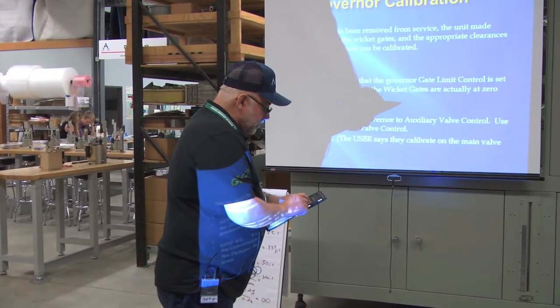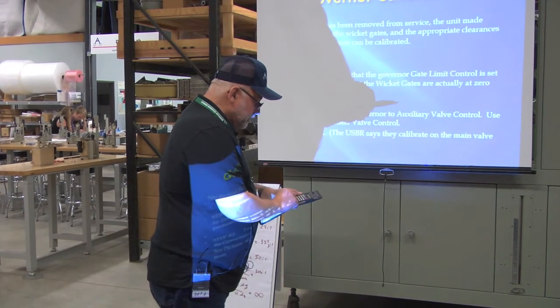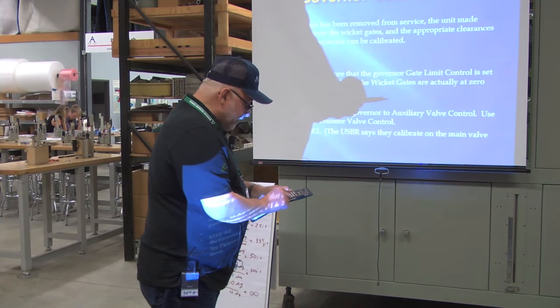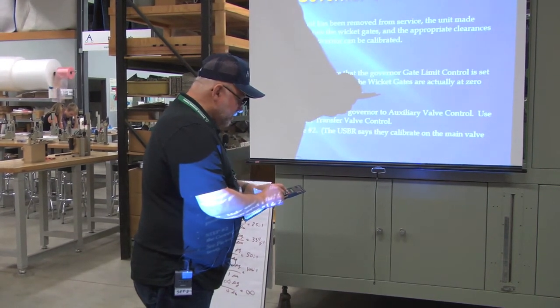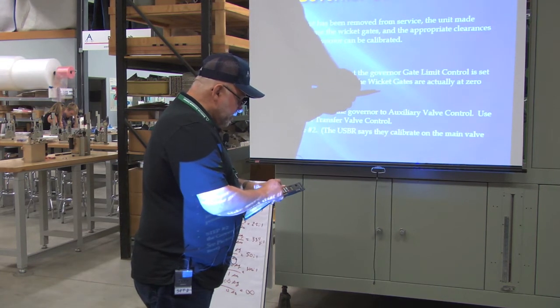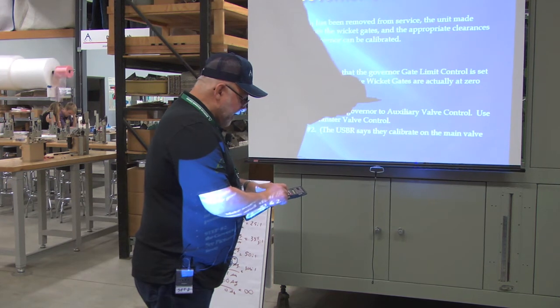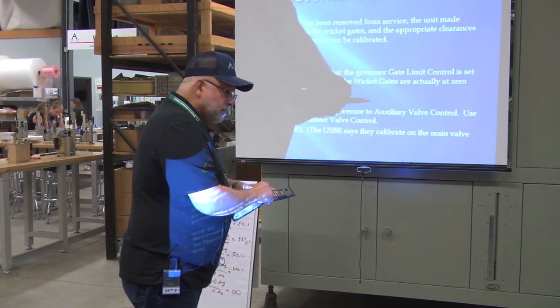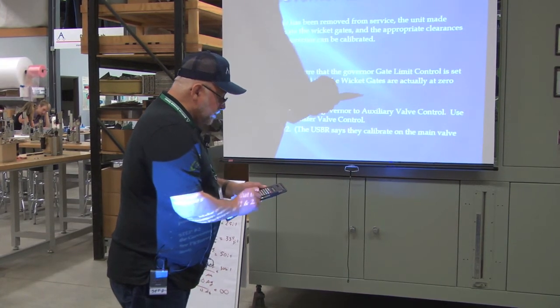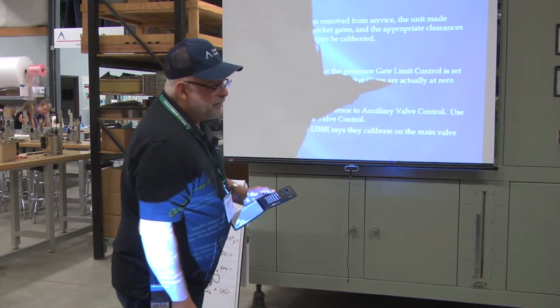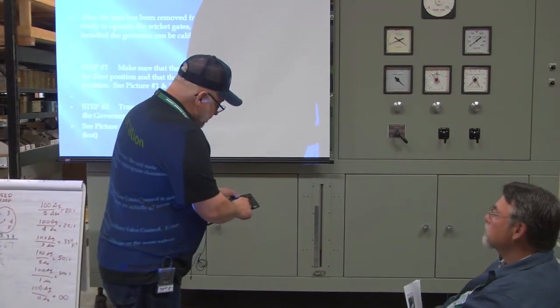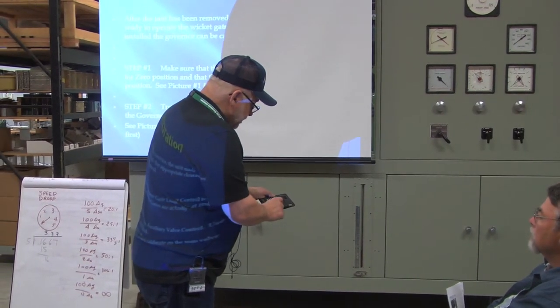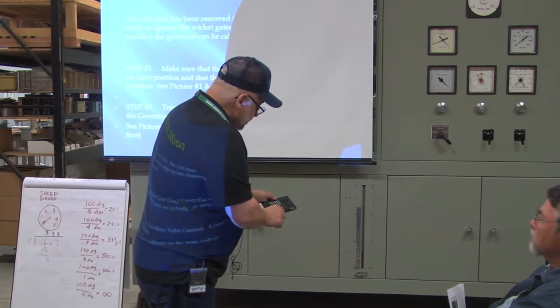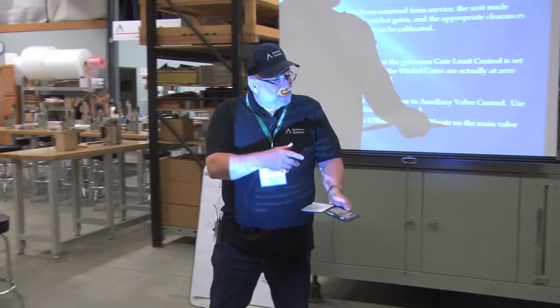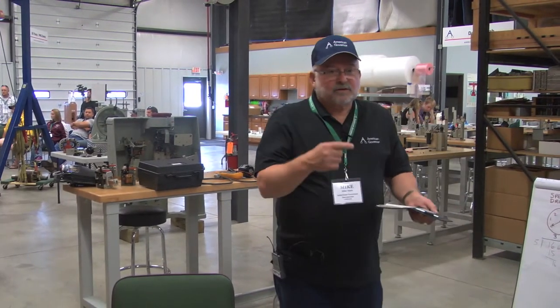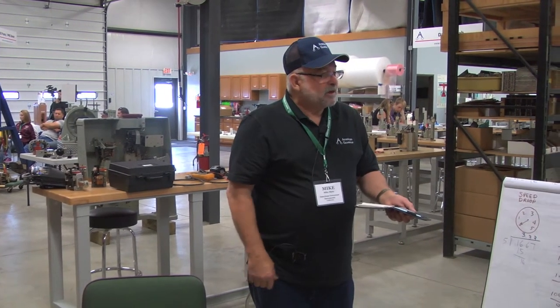All right, so you go 7,200 divided by, what do you say, 81 and a half? 81.8. 7,200 divided by 81.8 equals, you got 88 poles. Okay, it'll work either way. So you got 88 poles. Any 60 cycle system, 7,200, divide the speed into it, that's how many poles you got on the unit. The more poles there is, the slower the unit.